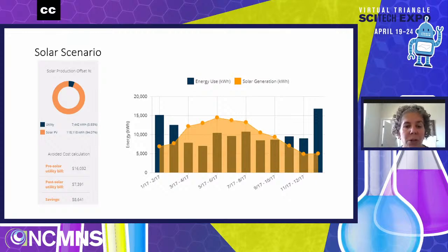So in June of every year, those utility credits are taken by Duke Energy. And you can see that in March and April and May, this array is overproducing and generating credits that Duke will eventually take and say, thank you very much, we appreciate that. But again, when this facility goes back online to its normal usage, the overproduction won't be as much. And you can see that the solar array will cause about $8,600 in savings. That's an estimate.